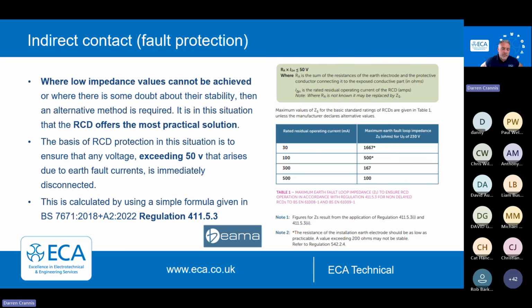So it's important that when we have, for example, commercial installations where maybe the boards are at far ends of the building, tucked away in risers, you might have long ring final circuits, long radial circuits, long lighting circuits. You can use RCD as fault protection. And you've got the values here, which is kindly given to us by BEAMA in this table. So you've got your 1667 ohm value for a 30 milliamp RCD. And they're absolutely brilliant in this situation where you just, should we say, need to go beyond those Zs values.